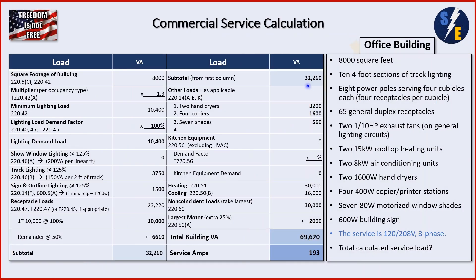Adding up all our bold numbers, we arrive at a total building VA of 69,620 VA. We have a 208 volt three-phase service, so we divide by 208 multiplied by the square root of three. The result is 193 amps — and that is our completed calculation. Once you have all the data, it's just a matter of plugging it in, and you can do a full office building service calculation in just a few minutes.